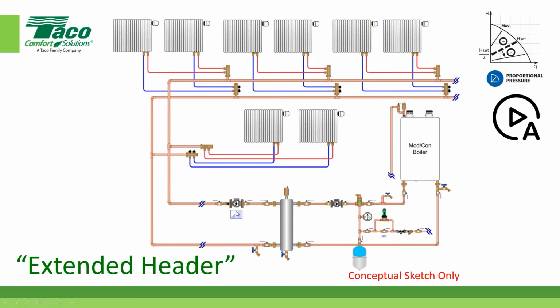Notice another thing that I'll say here. Generally, a lot of these systems, because they're thermostatic radiator valves, they don't have end switches that come back and shut things off, right? So that's another consideration there for why this circulator might want to run continuously while there is a possibility of a call for heat. We'll say that the only thing that brings these two circulators on would be the outdoor sensor of this particular manufacturer of condensing equipment. Could be any brand, but some of them push that more than others.